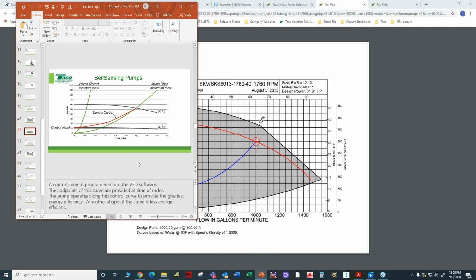And they use multiple differential pressure sensors, and they take the most remote reading, and they have some kind of logic that they take one of those readings to control their pump. It's a bit sketchy because it's not clear which one of those DP sensors should be the right control signal. And that's one of the benefits of a self-sensing pump. It does not need a DP, differential pressure transmitter location. It does it all through software. So it's not necessary to have that out there in the pump operating characteristics of a self-sensing pump. Good stuff.